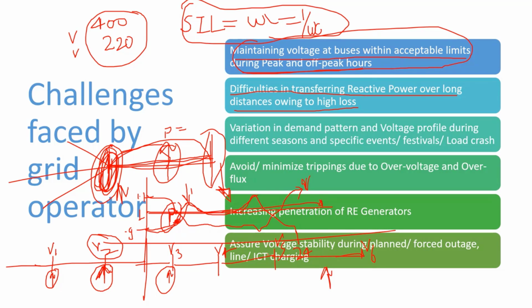Because for movement of this reactive power to balance this power, I have informed you that if V1 is greater than V2, then the reactive power will flow from the higher voltage to the lower voltage. The reactive power will be like this. Okay, so just assume that this is operating at 0.6, this point is 0.8, this is 1.1, this is 1.2 and this is 1. So just tell me whether you will be able to transfer reactive power from this part to this part. No. Reactive power will go from 1.2 to 1.